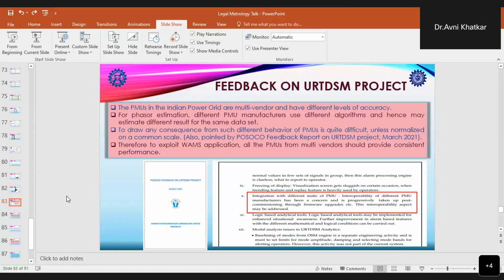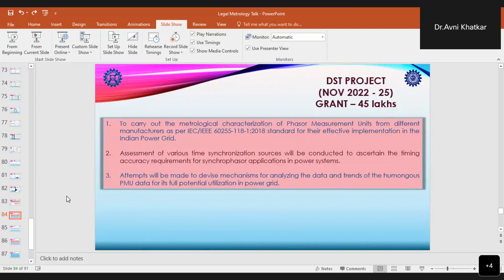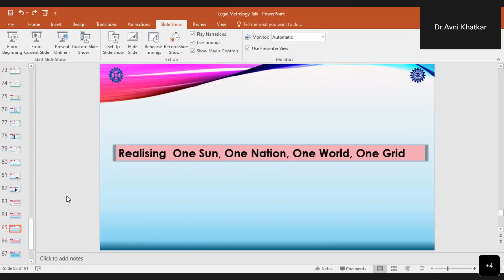Therefore, to exploit them in the WAM applications, all these PMUs from different vendors should provide consistent performance. On the basis of this feedback, we are also undertaking a DST project of 45 lakhs in order to carry out the metrological characterization of these PMUs from different manufacturers as per the latest IEEE standard for their effective implementation in the Indian power grid. Also, in this, assessment of various time synchronization sources will be conducted in order to ascertain the timing accuracy requirements for synchrophasor applications in power systems.